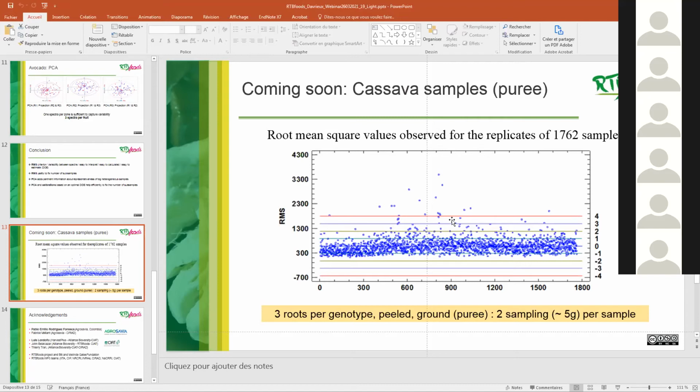Of course it's important to do that, but it's also important to go a step ahead and do the calibration. The advantage of NIR is that you can scan easily. When you want to do calibration, especially for something like carotenoid, a complicated constituent to determine in the lab, it's important not to spend too much time on spectra. You always have time to select, as we have done here, to remove all the incorrect spectra and do the calibration with the others.